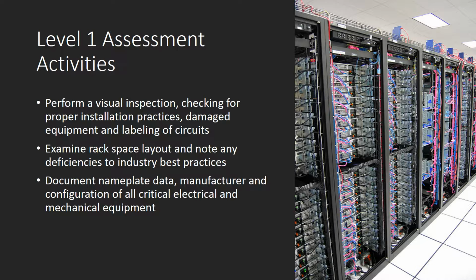Just as in the introductory assessment, the Level 1 assessment will include a visual inspection of the site, checking for proper installation practices, along with any damaged equipment and the labeling of circuits. Next, the rack space layout will be examined, and any deficiencies to industry best practices will be noted. All of the nameplate data, the manufacturer and configuration of all critical electrical and mechanical equipment, will be documented.